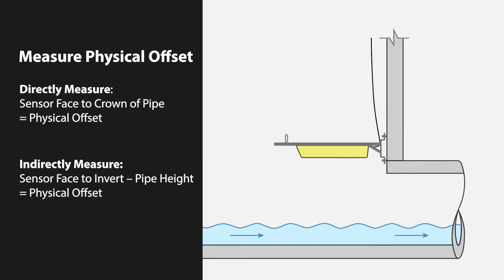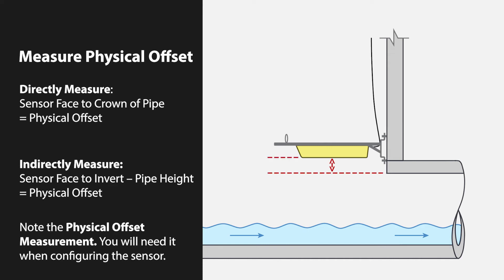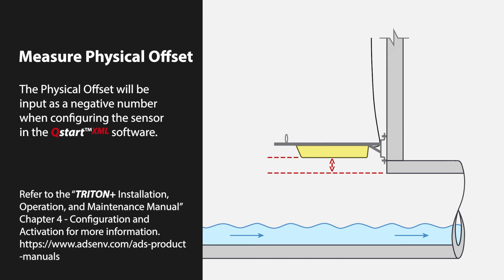To measure indirectly, measure the distance from the face of the sensor to the manhole invert below the front portion of the sensor, and subtract the pipe height from this measured distance. Note the physical offset measurement. The physical offset will be input as a negative number when configuring the sensor in the ADS QStart XML software.